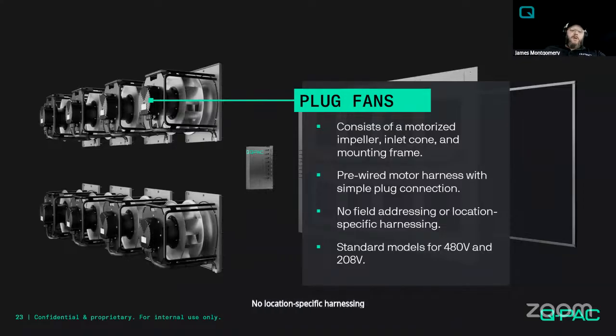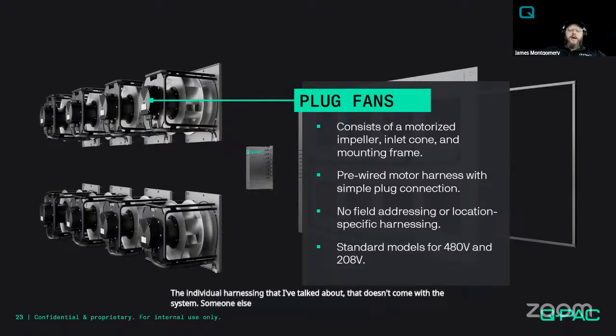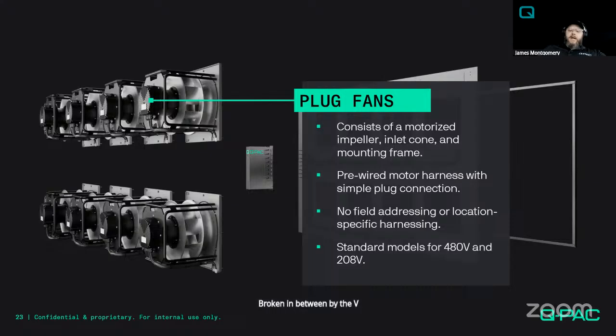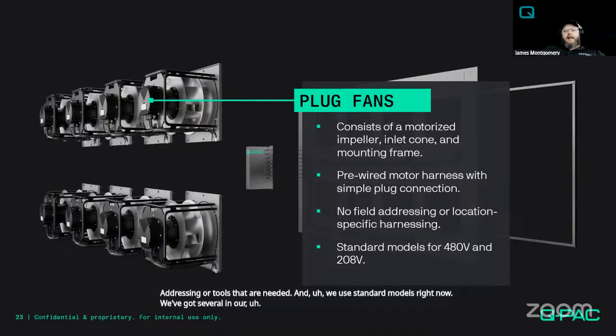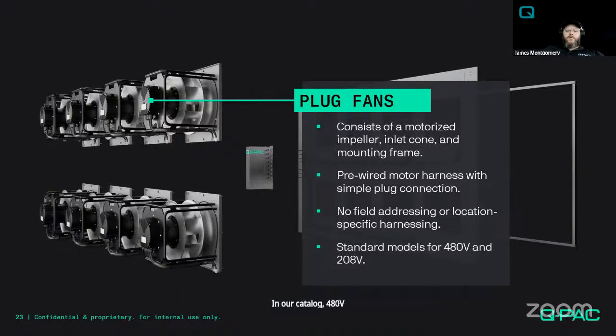A lot of times when arrays are bought, the individual harnessing that I've talked about doesn't come with the system. Someone else has got to include that in their scope, and they've got to build that by hand. And that's going to be at least 2 runs of conduit, high voltage and low voltage, to get these systems running. In an AC motor, it would just be one, broken in between by the VFD. But again, no field harnessing or any location specific addressing or tools that are needed. And we use standard models right now. We've got several in our catalog, 480 volt and 208 volts, or 230 if you prefer. 3-phase, to be correct there.